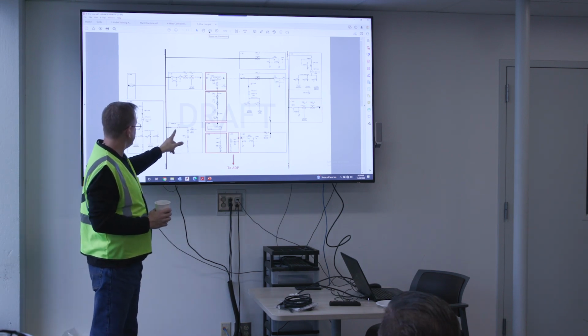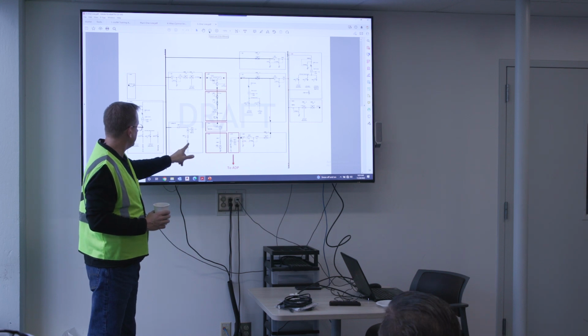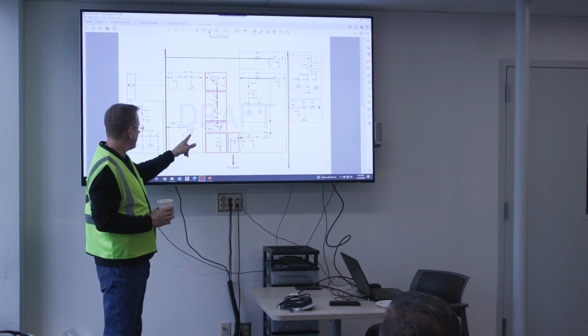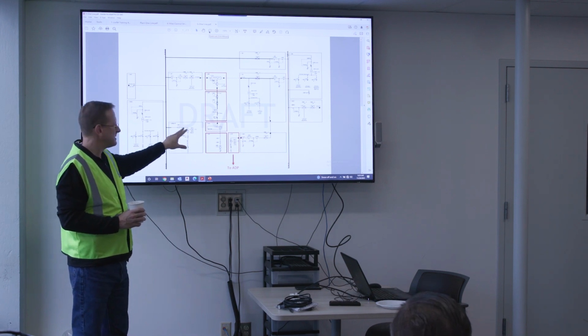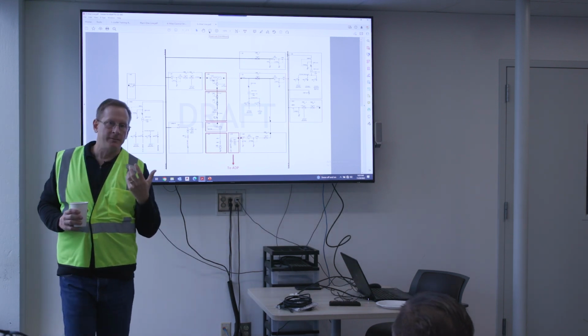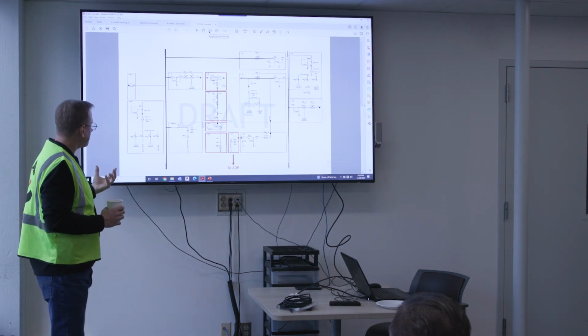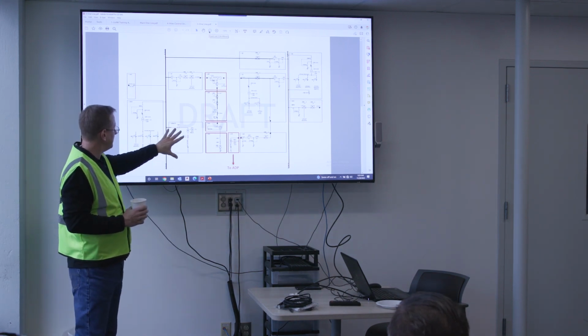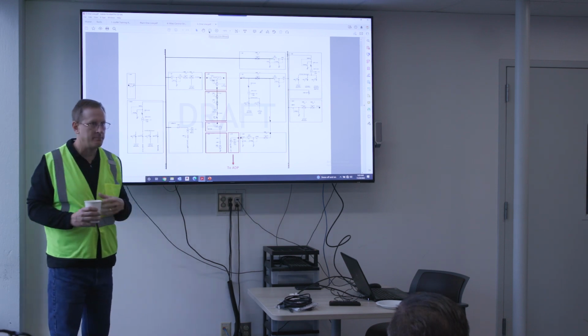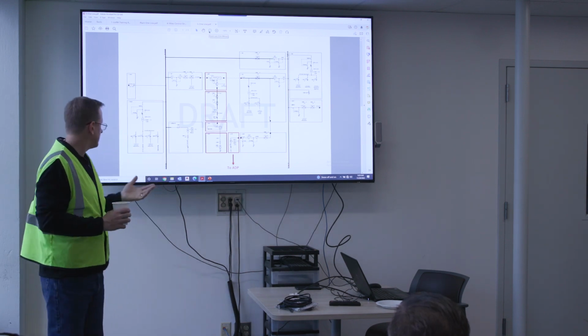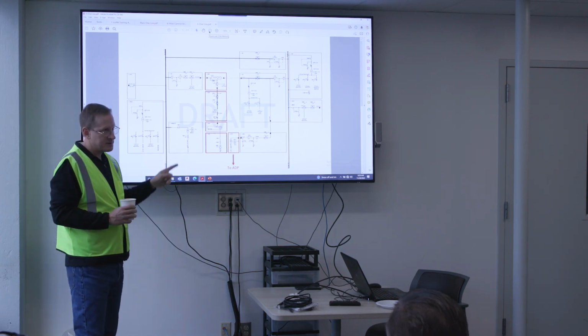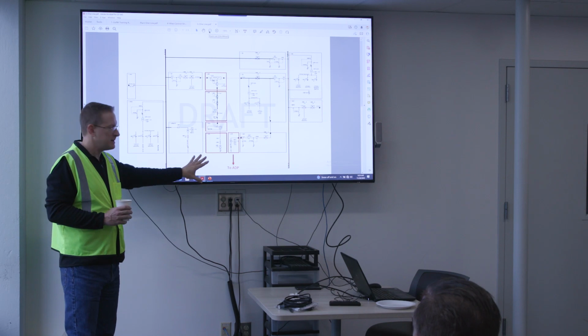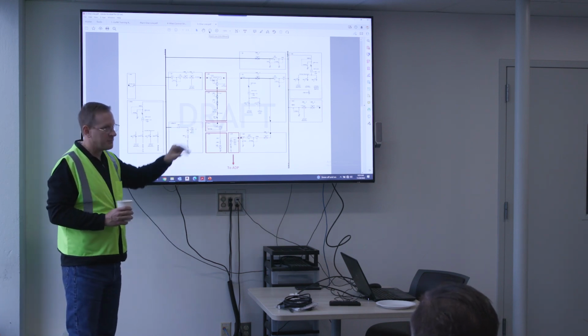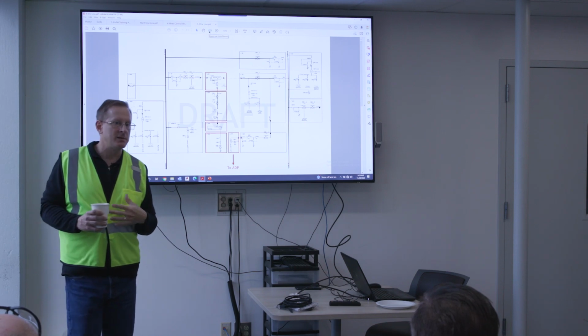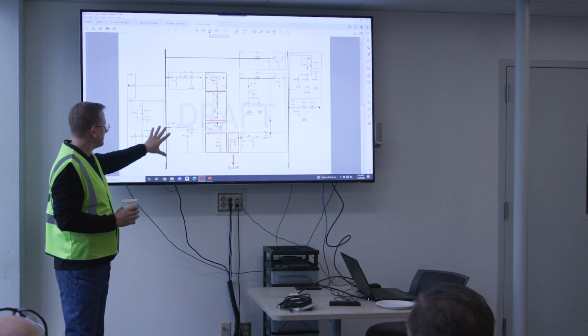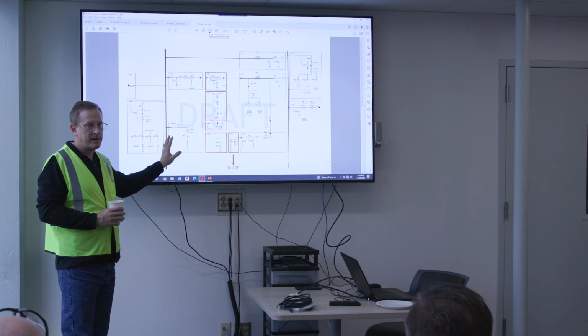We do have a tap off of here into another transformer. This is about a 45 kVA transformer from 4160 to 480, because there are certain 480 volt loads that will be used by our system that are fed from the utility, basically for starting. Also, the preheat system that we use to preheat the diesel comes from this feed, because that's the utility feed. We don't need the output feed for preheating, because at that point the diesel is running. We only need preheating when the utility is available, so we can just use a utility feed for preheat and pre-lube as well.